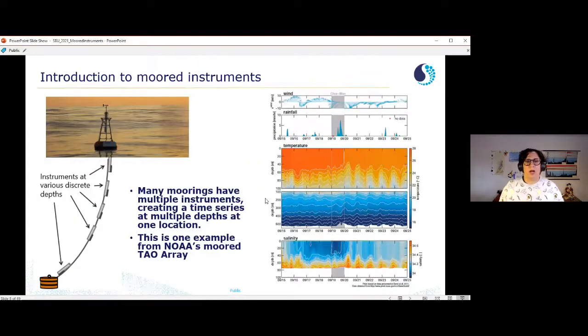Okay, so introduction to moored instruments. The MicroCAT that I'm going to show you in a minute, we usually put them in the ocean, and they're usually static. So they're taking a bunch of data at one location for a long time. This can be anywhere from a week, 6 months, or 2 years. And we've even had some that have managed to take data for 10 years.